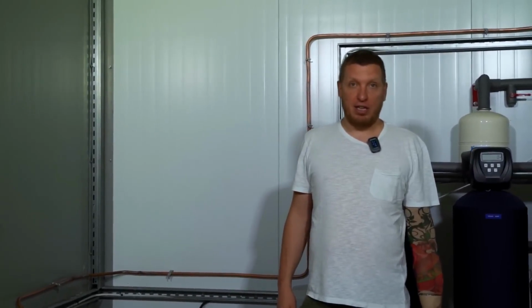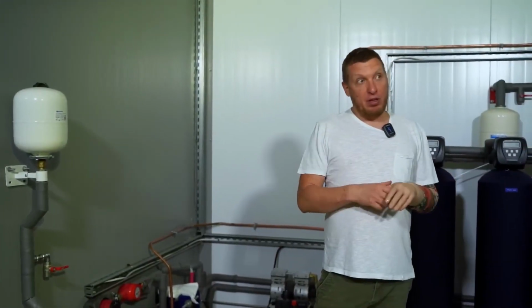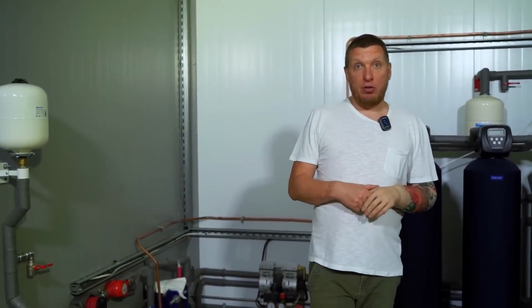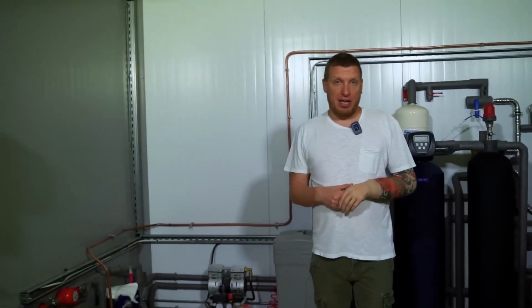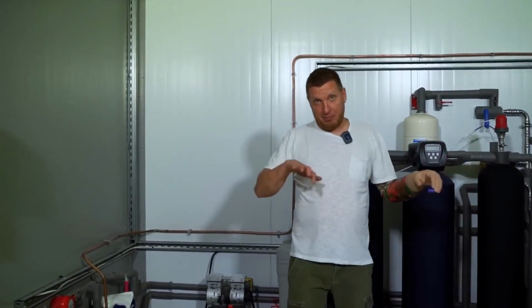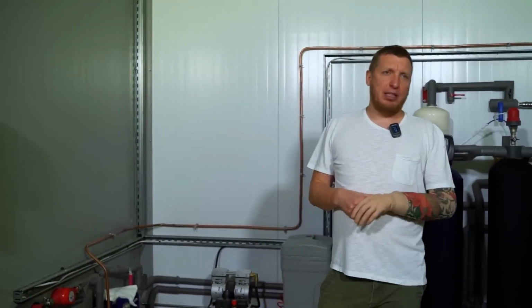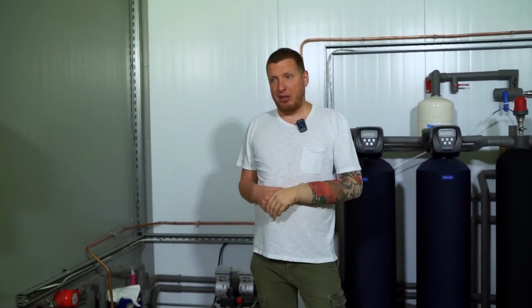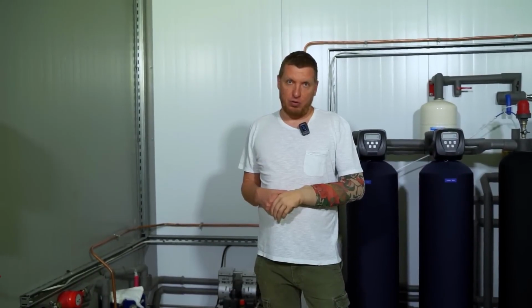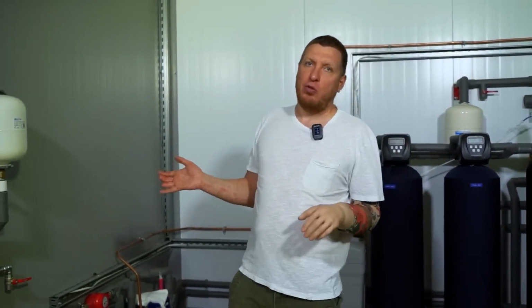And sometimes you have to install a heat pump simply because even if you have the money and are willing to pay for electricity, you just don't have enough power available. Here, the heat pump saves the day because it only needs a quarter of all that. As for the price, half the cost of a classic heat pump with a geothermal loop is the work for drilling the loop and its piping. This is when HDPE pipes are buried in the ground. Basically, no matter what anyone says, you can't get more than 30 to 35 watts per meter from the ground. Some part of the loop will eventually freeze through. A meter of drilling costs at least 1,000 rubles.